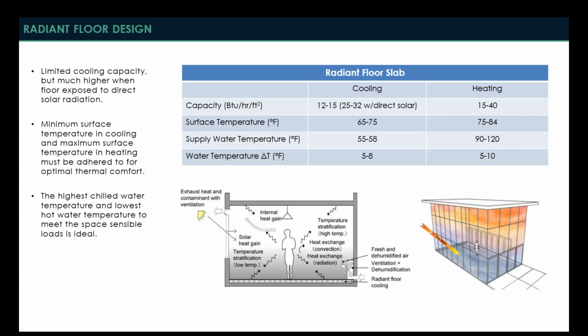In cooling, you really don't ever want to take that temperature below 65 degrees. Anything below 65 degrees, people are going to start to have literal cold feet, and they're going to start to experience this radiant temperature asymmetry, and they're going to be uncomfortable. And the same is true on the maximum end for heating. So 84 degrees is about the highest you would want to go with a radiant floor slab before, again, people's feet are going to be warm and they're going to be uncomfortable.